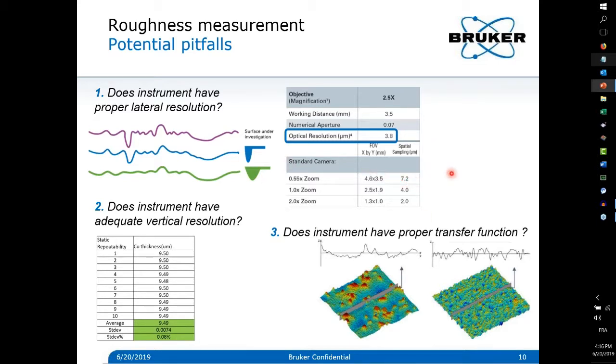However, because we use digital cameras, and zoom, we can end up with a pixel size around 7.2 microns. So here is really what the camera can see. And in that case, the limitation is not the objective but the camera itself. So in that configuration, we will only see 7 microns. So any details of 4 microns will absolutely be smeared out and will not be shown.